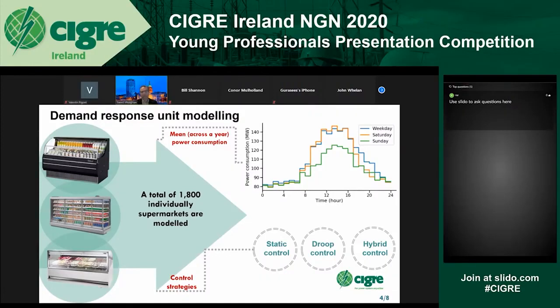In the static control, we switch off the entire fleet if the frequency exceeds the predefined threshold. In droop control, we change the temperature based on the frequency deviation. Indeed, it's akin to conventional generator droop, except that we change the temperature set point. So when the frequency goes down, we increase the temperature set point, and in that way we indirectly reduce the power consumption. In hybrid control, we change temperature set points based on the frequency deviation and the derivative of the frequency deviation.